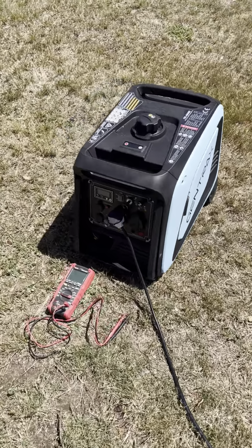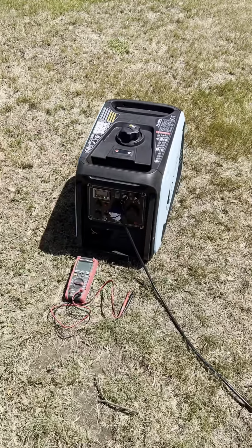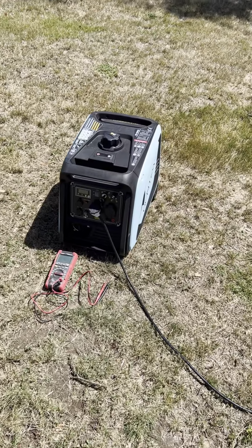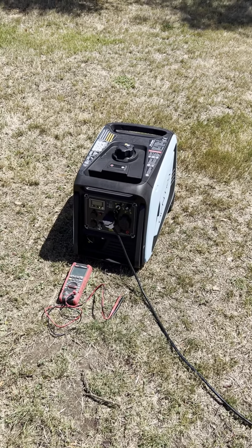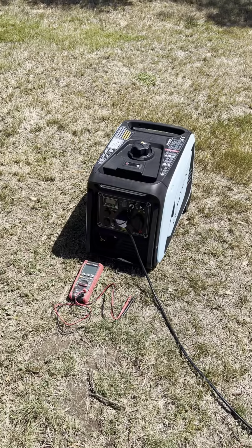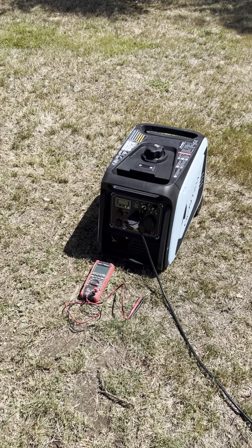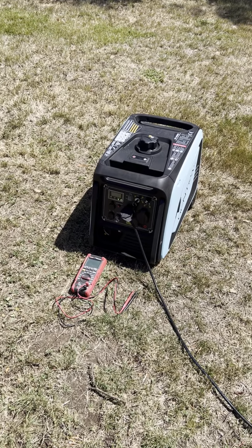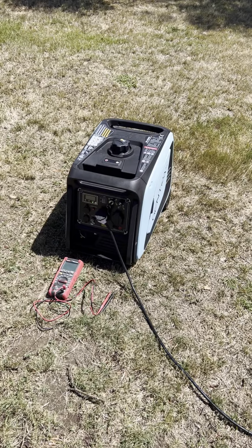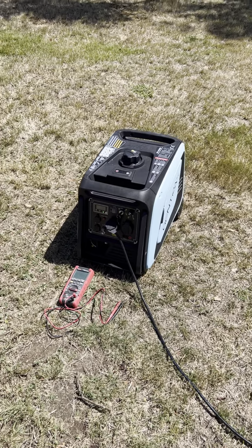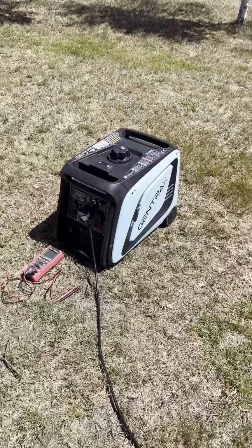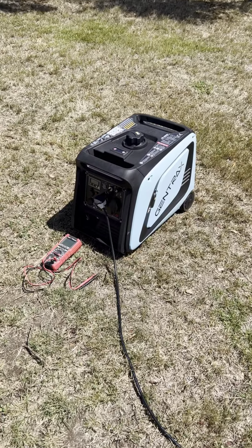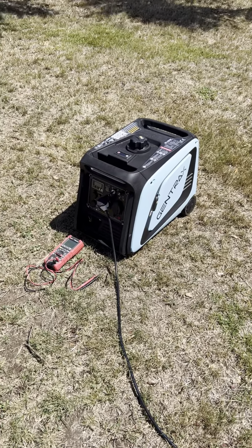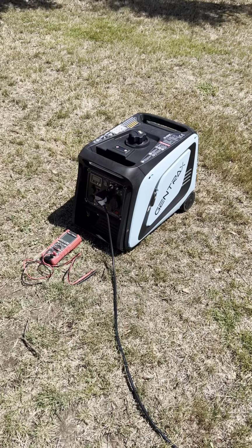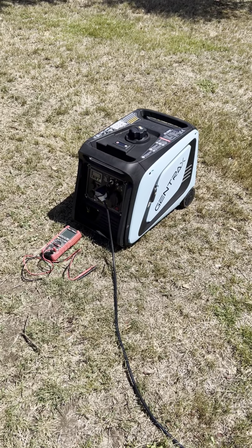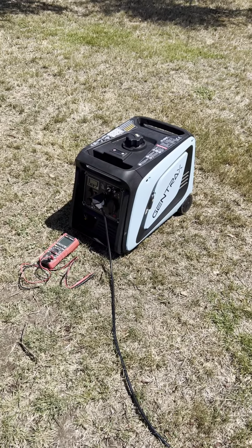I'm going to have a look now. Remember, we've got a resistive load on this, so there's no high inrush current - it's basically fixed, I just go up. It's not like starting a motor where it's got multiple times the load, not doing anything like that, just a resistive load starting up. It runs the fridges and stuff fine, lights and all that, but I do notice that the LED lights flicker when the heating element cuts in. So with changing load, it's not real good at handling that.